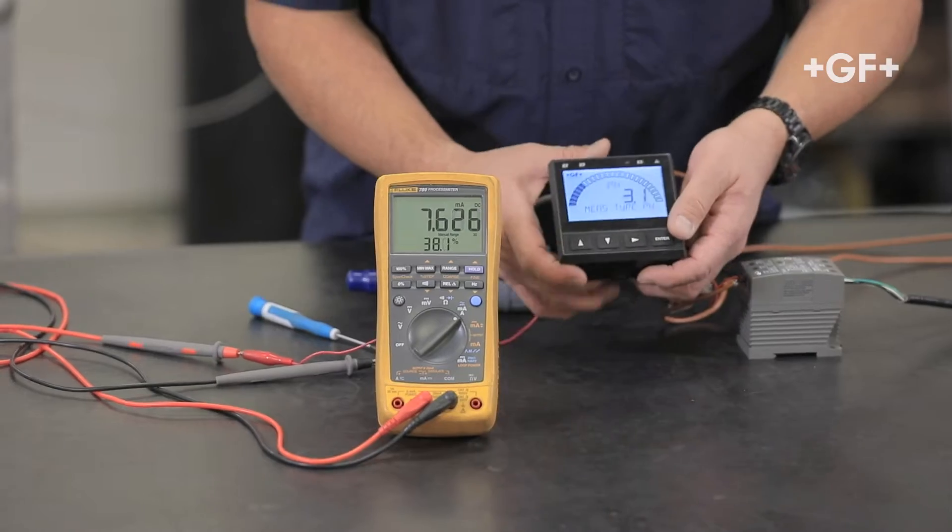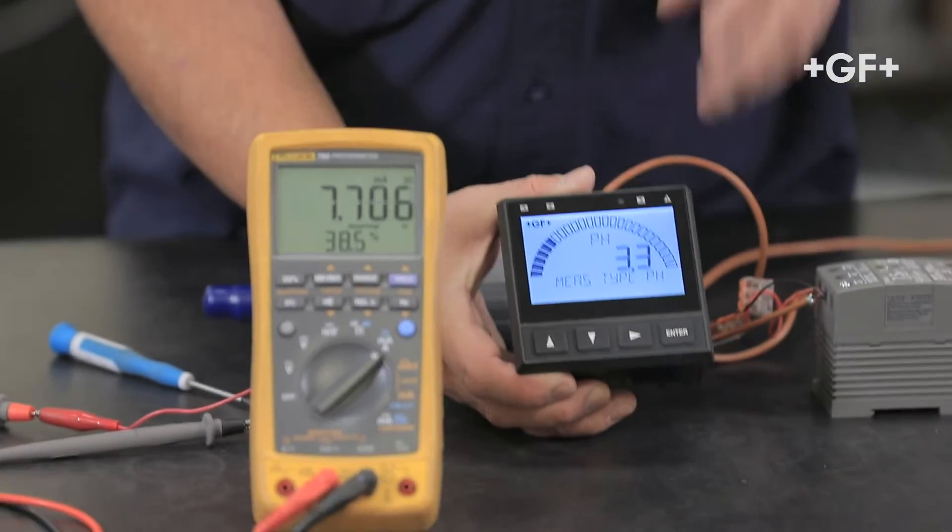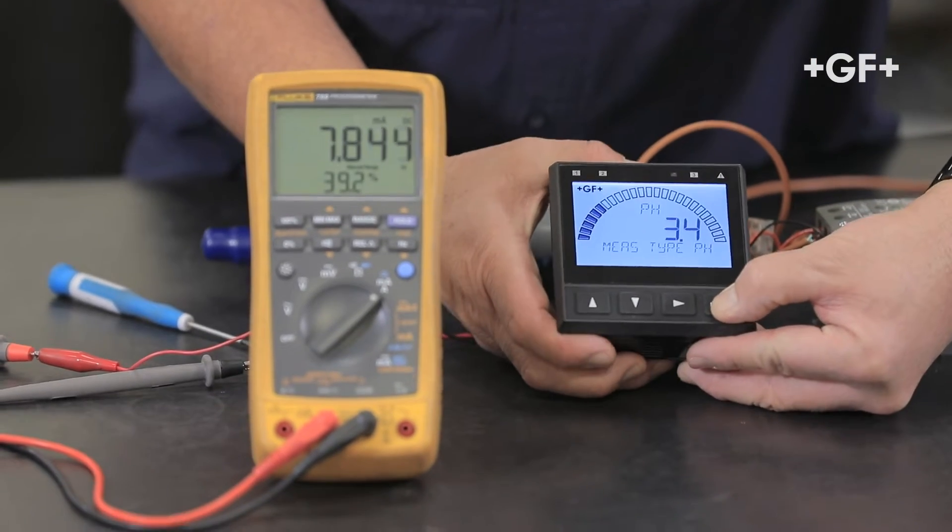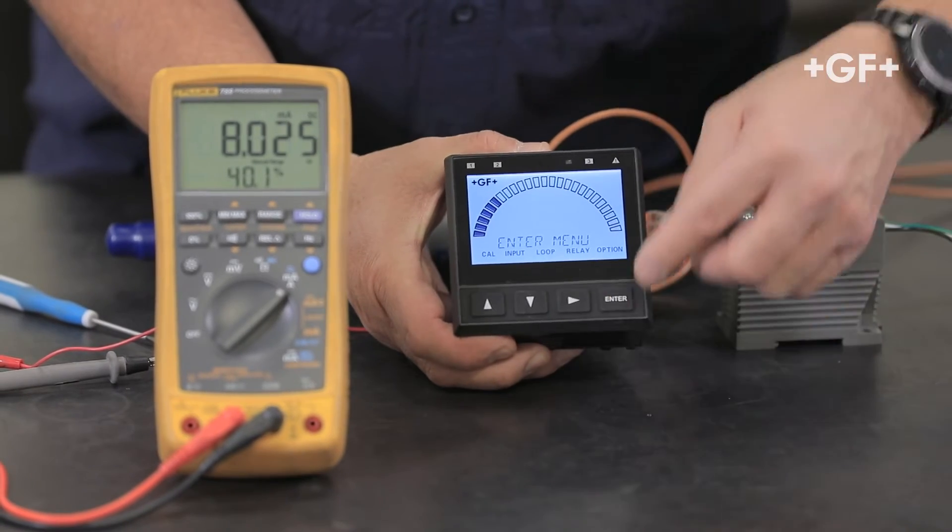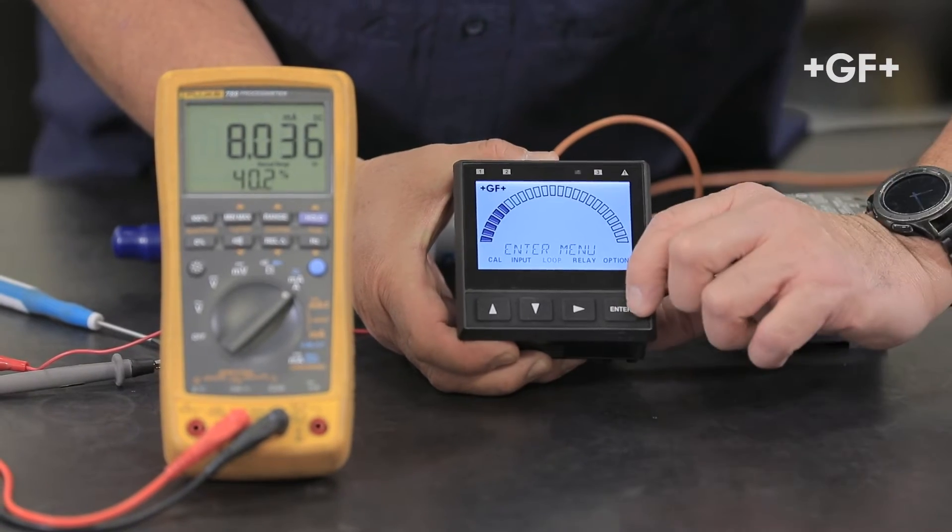Okay, and what we're going to do is scale our 4-20. So for pH the default scale will be zero to 14. Press and hold the enter button, arrow over to the loop menu, press enter.